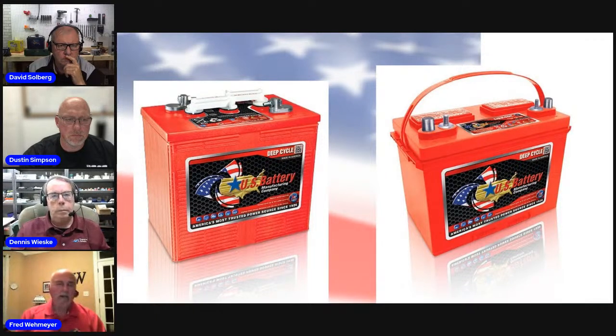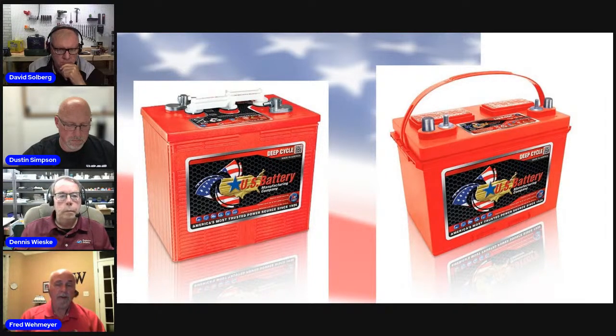The other reason 12-volt batteries are available in smaller ampere hour capacities, versus 6-volt batteries in larger capacities, is basically weight. If you built a 12-volt battery at 200 ampere hours, it would be pretty heavy, well over 100 pounds, and that's hard to move in increments. So if you need capacity beyond 100 to 150 ampere hours, it's typically better to go to a 6-volt battery, even though we do make 6-volt batteries with up to 400 ampere hours. But that battery weighs over 200 pounds, so you're not going to move it very easily.